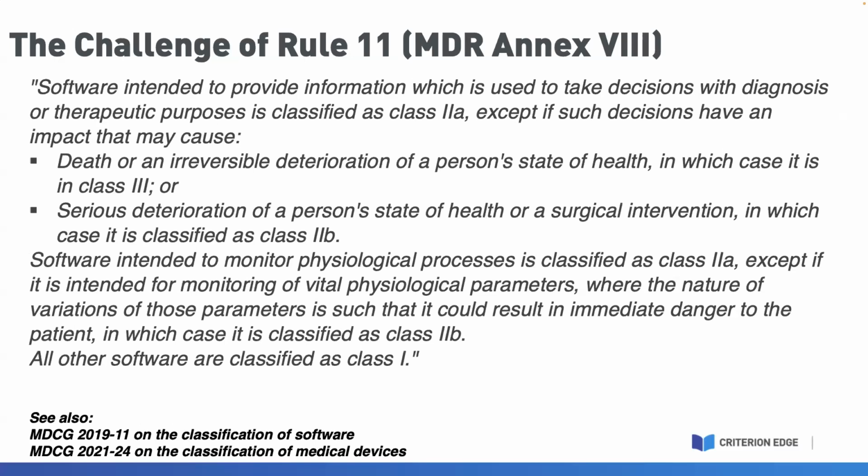So Rule 11 in and of itself is incomplete, and it assumes that all critical software is really either diagnostic or therapeutic, but that's not true. And it does open up a possibility that if you have software with a potentially high risk of injury that doesn't fall into the higher risk class, it could by default get classified as class 1, and you don't want to take that approach. You always want to aim higher, not lower.